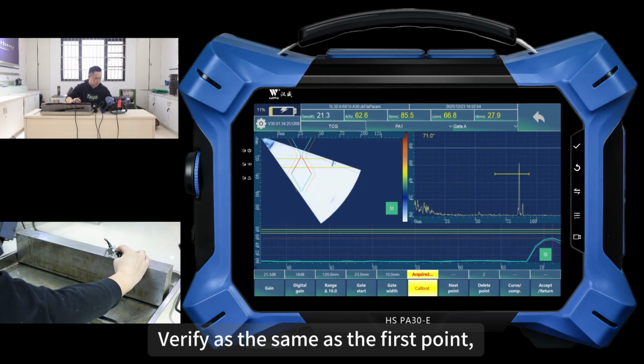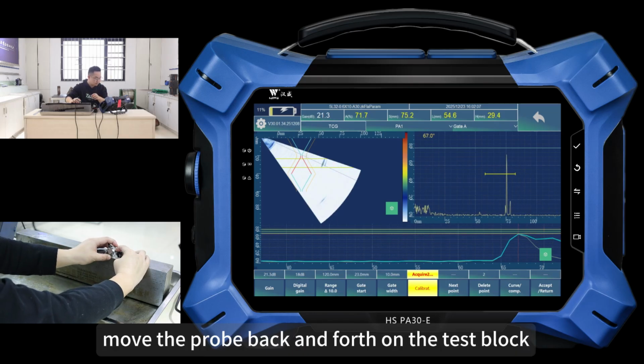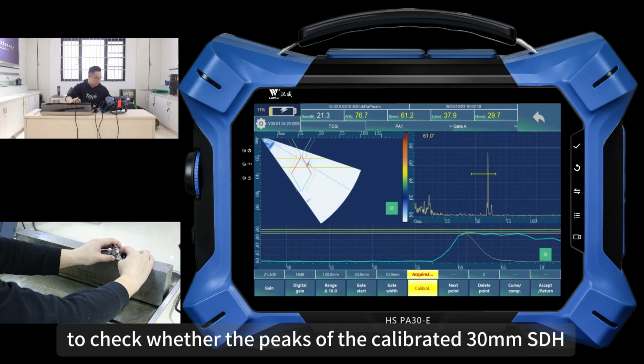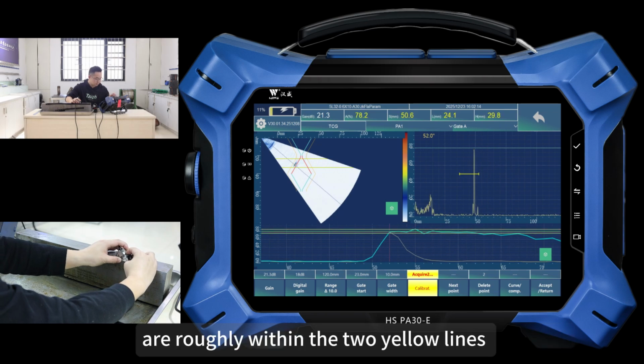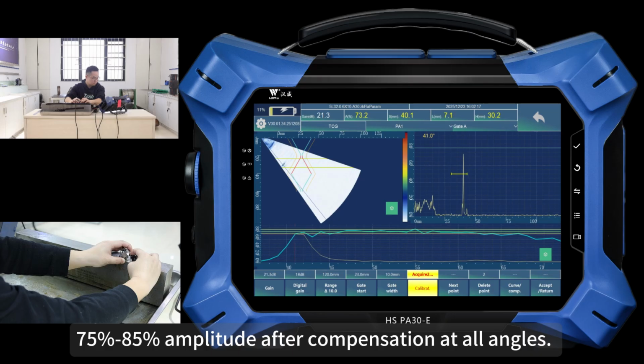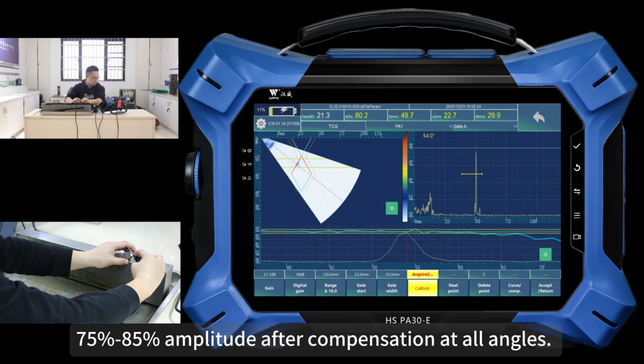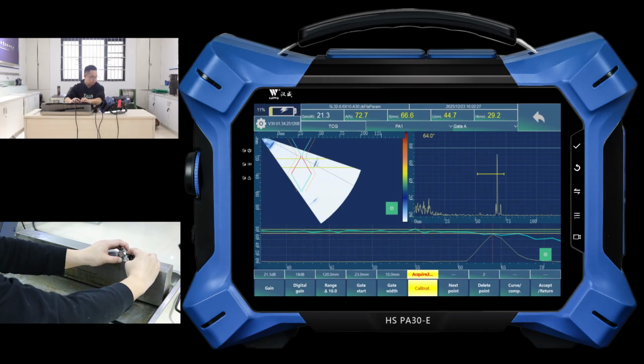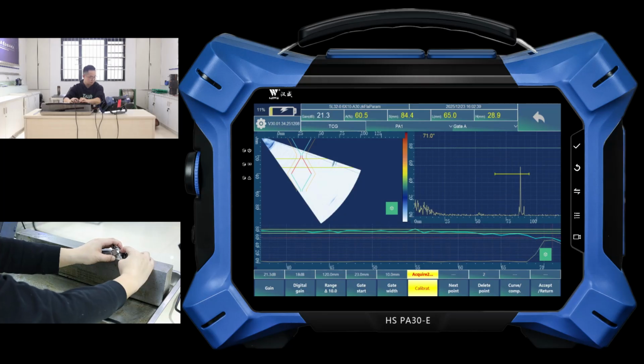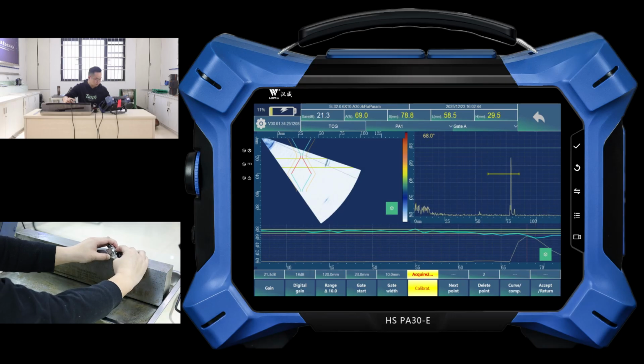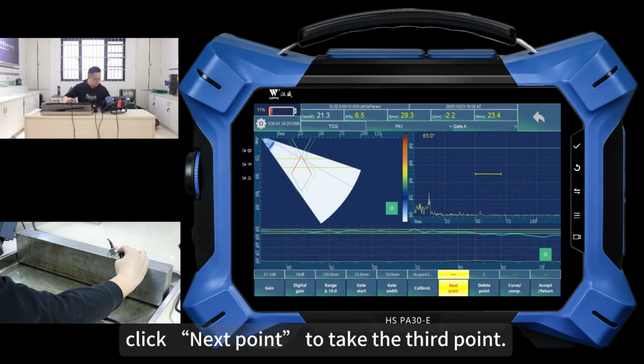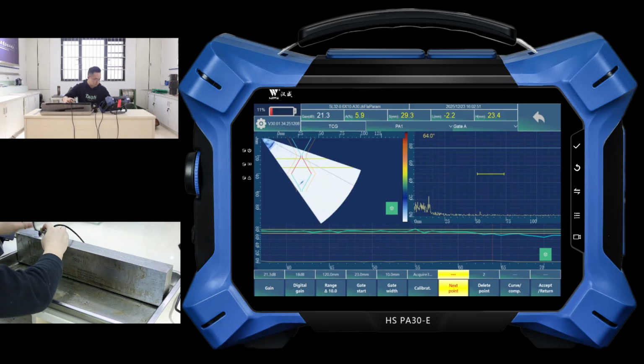Verify as with the first point. Move the probe back and forth on the test block to check whether the peaks of the calibrated 30 mm SDH are roughly within the 2 yellow lines. The amplitude should be 75% to 85% after compensation at all angles. If calibration is successful, click Next Point to take the third point.